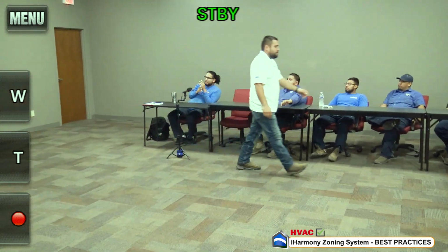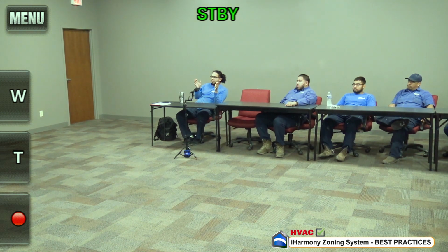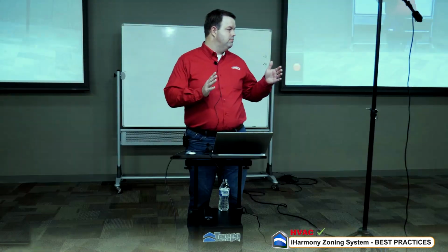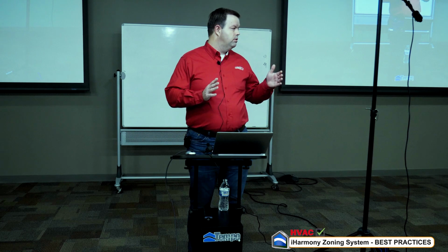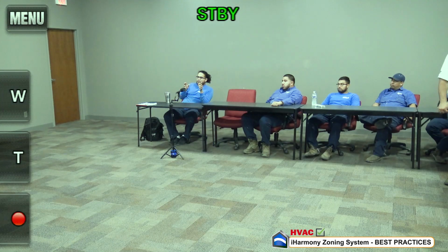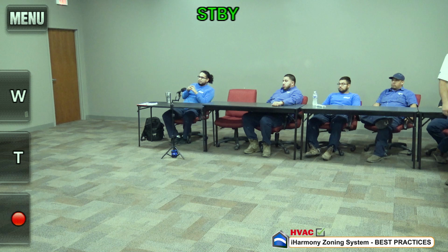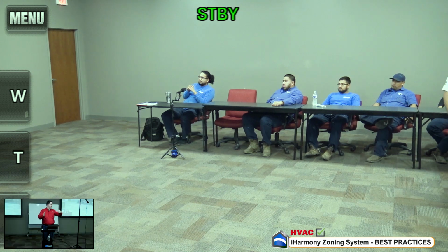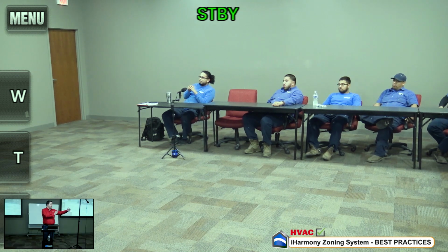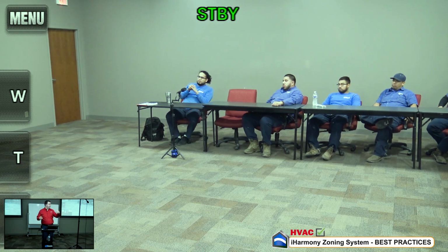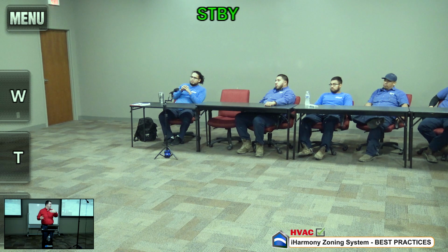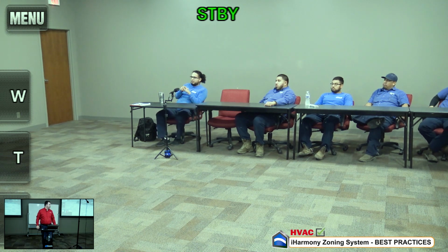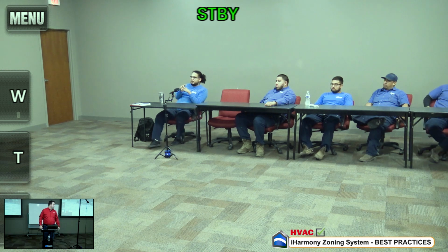So 11 inches is the max? Is that what you're saying to come out? It's like a starting point, essentially, and you pull out from there. You've got your plenum, you're going to stick the tip of it in, and 11 inches of it is going to be sticking out of the plenum. Okay. And then from there, you can adjust it inside the plenum, put it further in if you need to. And you're going to base that off the main thermostat.